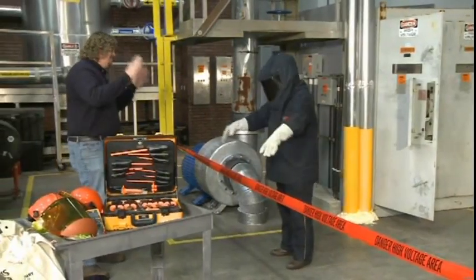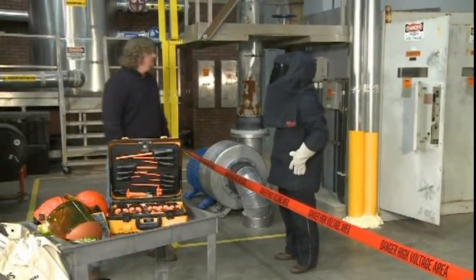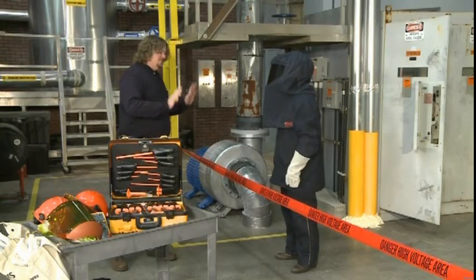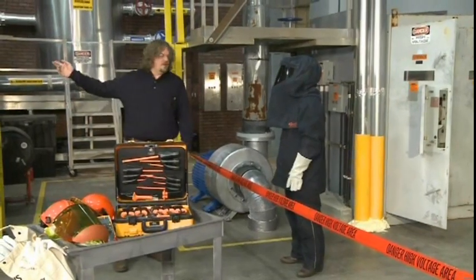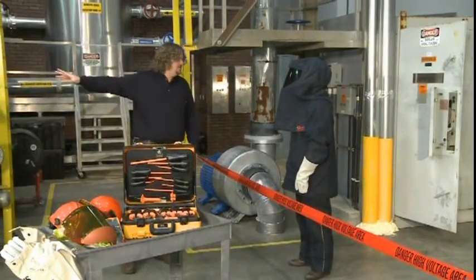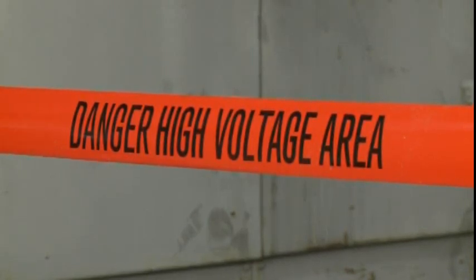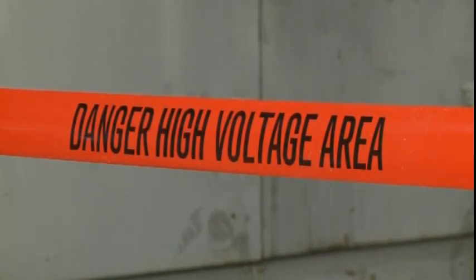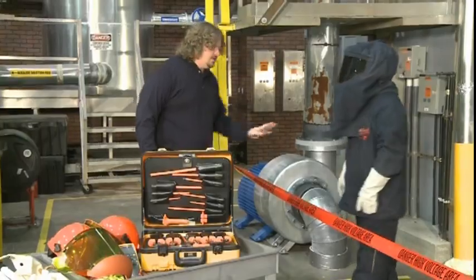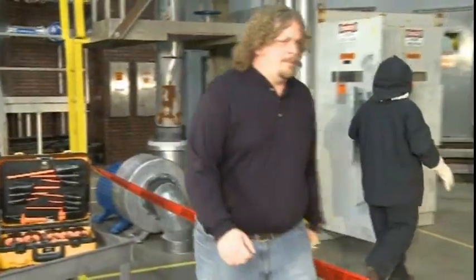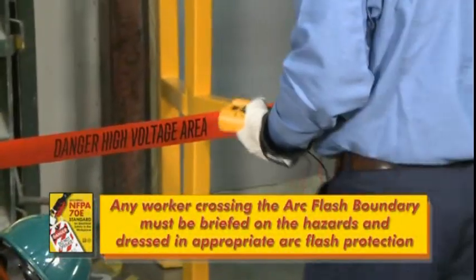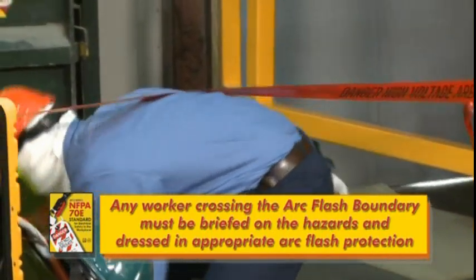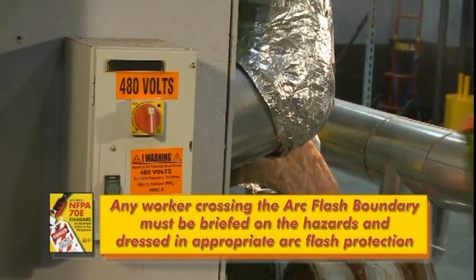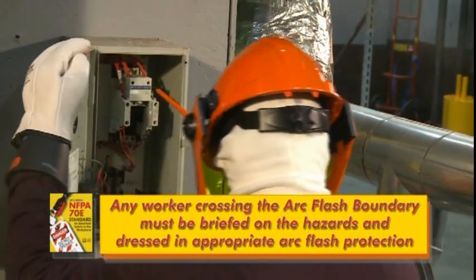In most instances, the arc flash boundary is the outermost of all approach boundaries and should be marked with barricading and hazard signage. A simple system which can be used to meet this requirement is using red danger high voltage barricade tape, which includes the proper signage. Any worker crossing the arc flash boundary must be briefed on the hazards and dressed in appropriate arc flash protection.